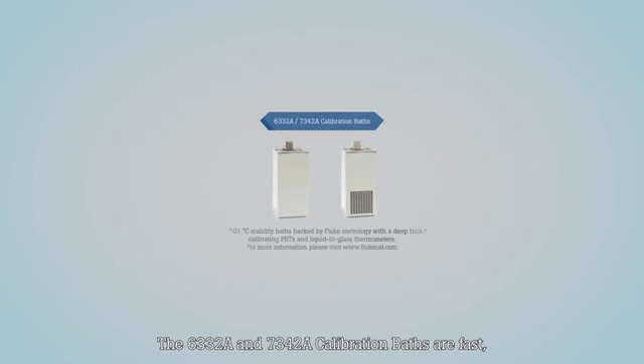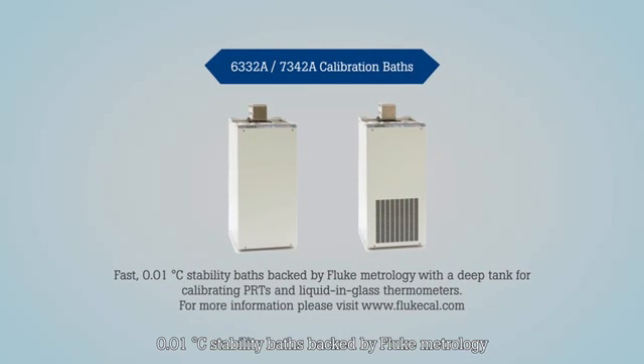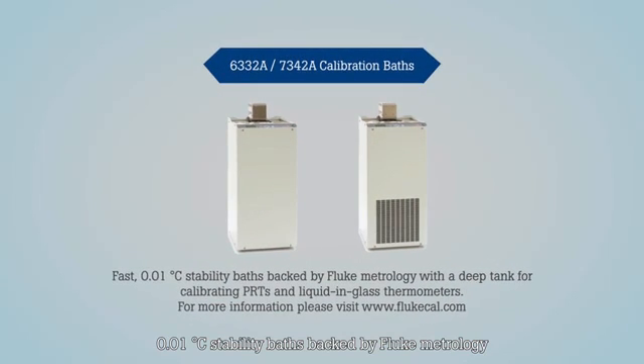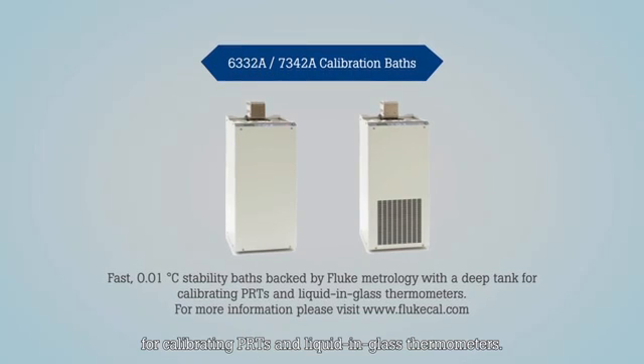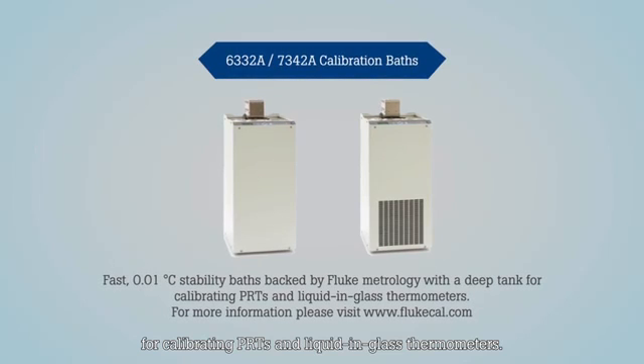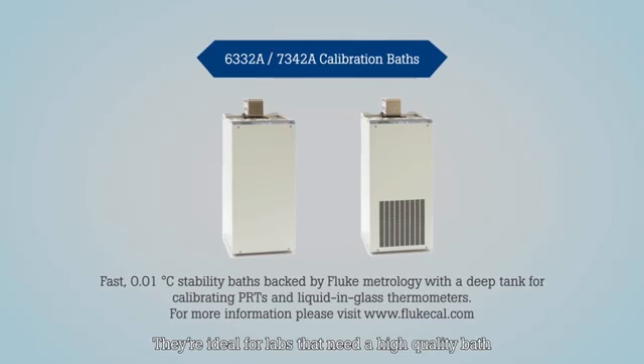The 6332 and 7342 calibration baths are fast, 0.01 degree Celsius stability baths backed by Fluke Metrology for calibrating PRTs and liquid-in-glass thermometers. They're ideal for labs that need a high quality bath with trusted specifications at an affordable price. Please visit our website for more information.